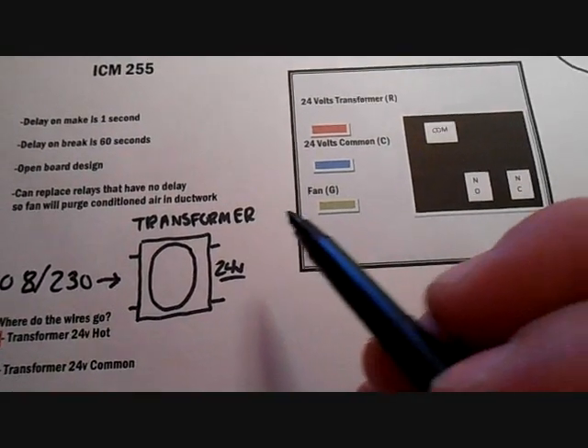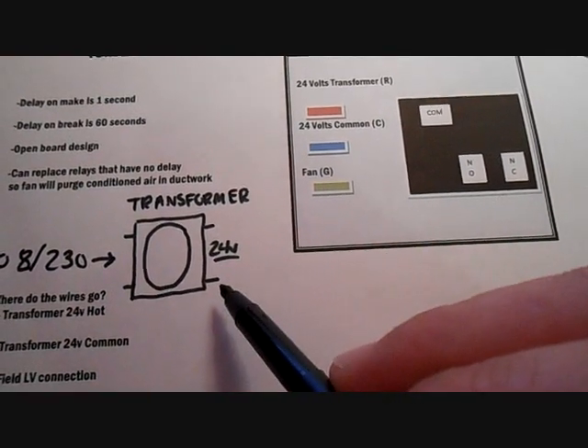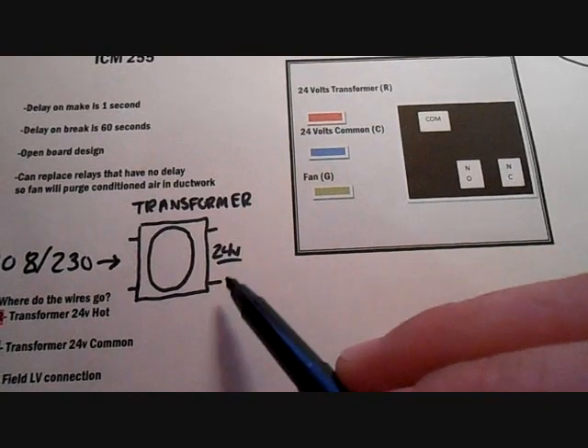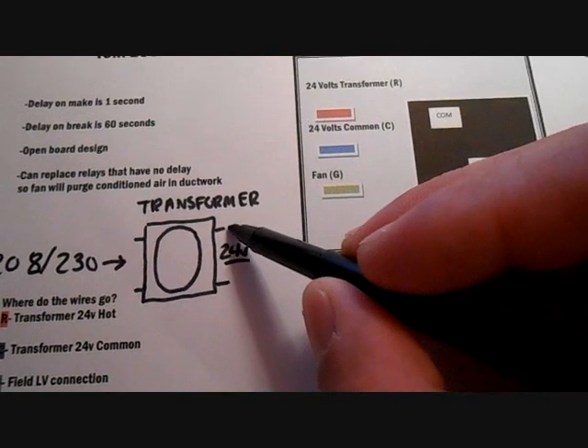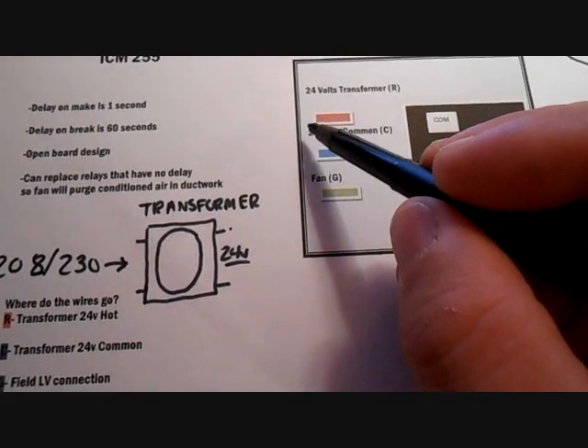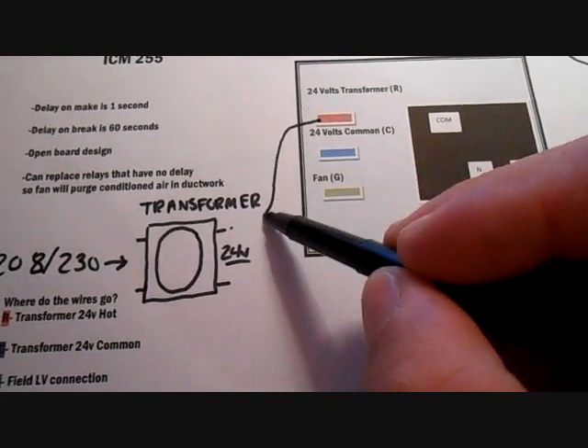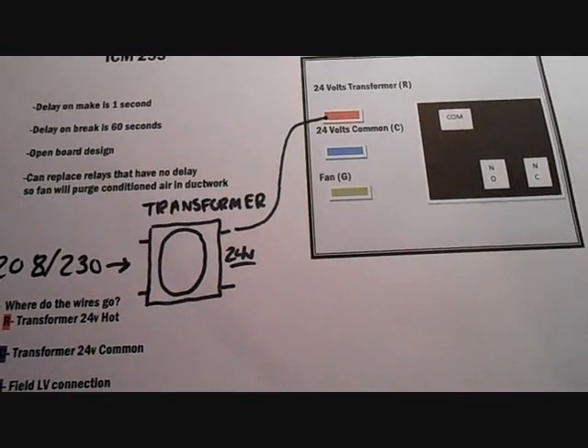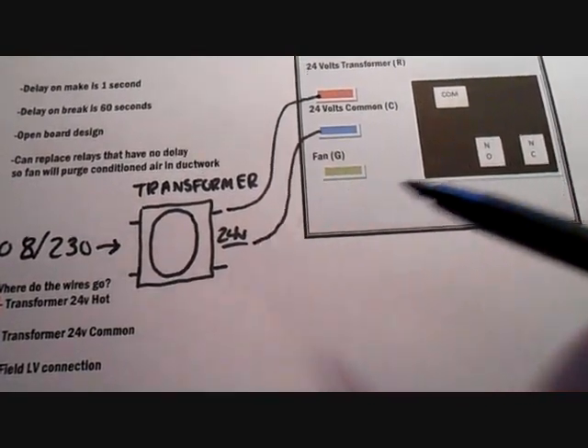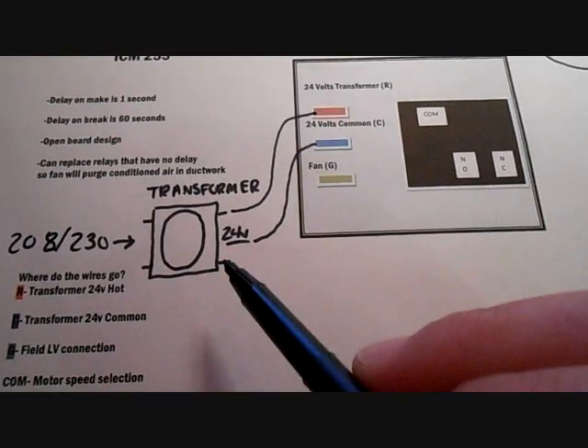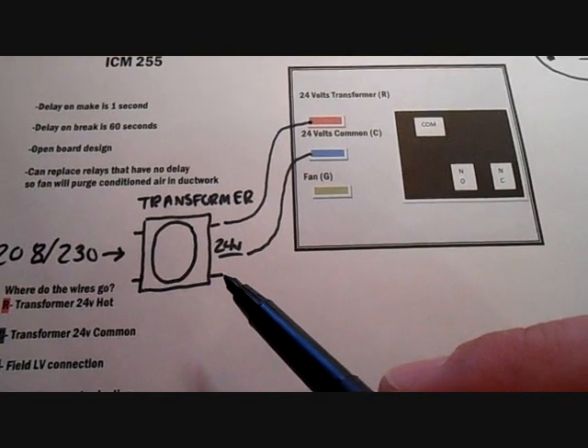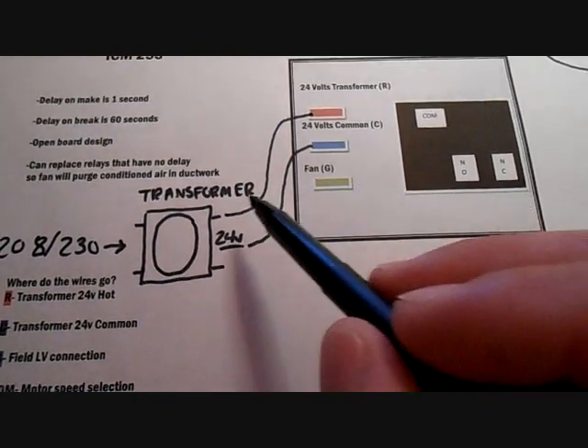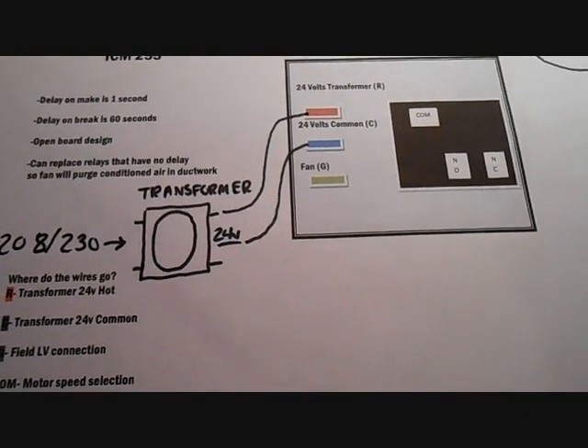And what we're going to do is one side of the transformer will be dedicated hot. One side will be dedicated common. It doesn't matter which one's which as long as it stays uniform throughout the system. So if we have one side hot, we have our 24 volts hot which is red, and it will come down here to that side of the transformer. By that same token, the opposite side will then be our common. That's where our signal will come from. And this signal can be taken from other parts of the low voltage circuit, as long as you can get the hot and the common signal from that part of the circuit.